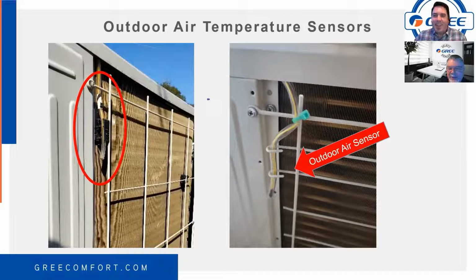135 degrees on the roof. Yeah, blistering. But a couple of things to remember about outdoor ambient sensors is it's important to locate the system so it senses proper airflow. So consider things like prevailing winds, sun exposure, other weather conditions, or things that may block accurate readings.